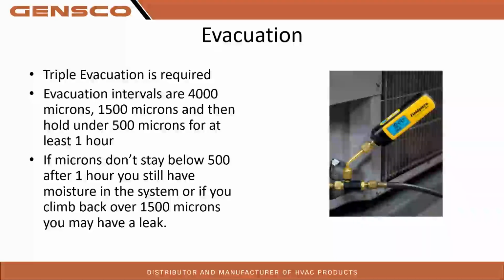The idea behind the triple evac is if you pull a vacuum too quickly on a system that has moisture in it, that moisture will actually end up freezing inside your line set. So the triple evac is to change the state of that moisture from ice back to a gas when you bring it back up to atmospheric pressure. It gives your vacuum pump a chance to pull that moisture out of the system. So that's what we're trying to do with the triple evac. And if you work on existing systems, doing it this way will actually help your system pull down a little bit quicker.